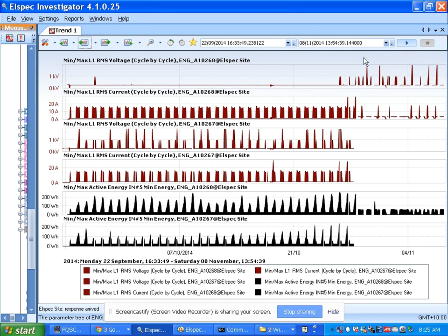So we've got maximum minimum RMS voltage, maximum RMS current, which is just maximum, there's no minimum. And then we've got the power consumed. This is an interesting graph, because you can see here the power requirements have changed. Now, I remember when I came into the shipping container, it was very, very hot. And someone had turned up to about 35 degrees, so it was heating the inside of the shipping container. And then now I see it's down to 28 degrees. So that's made a big difference. You can see that the current has dropped right down, and the overall energy consumed has dropped right down too.